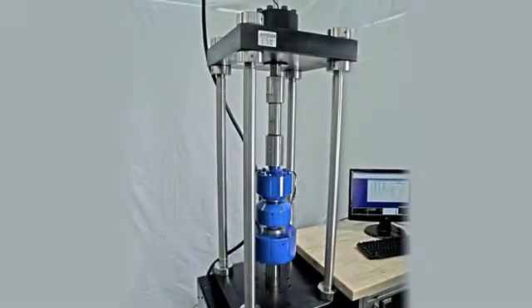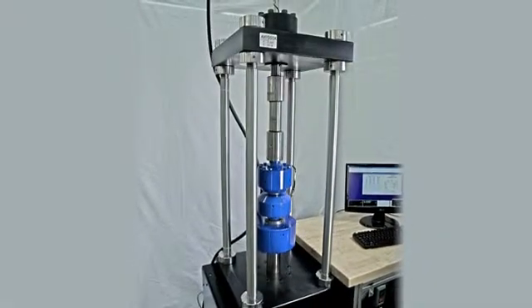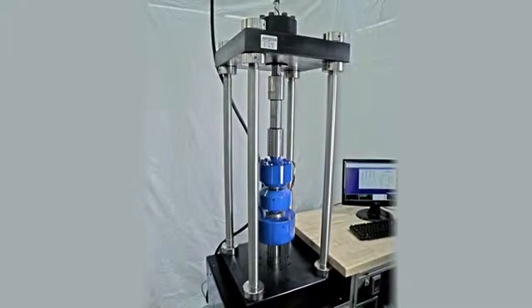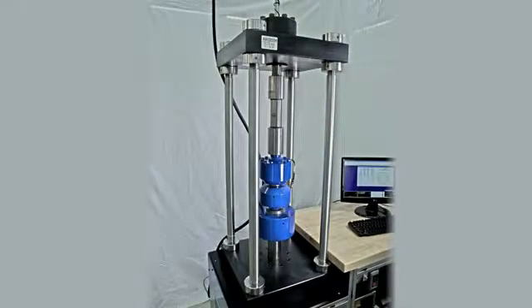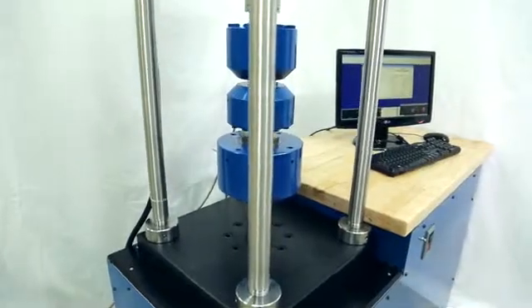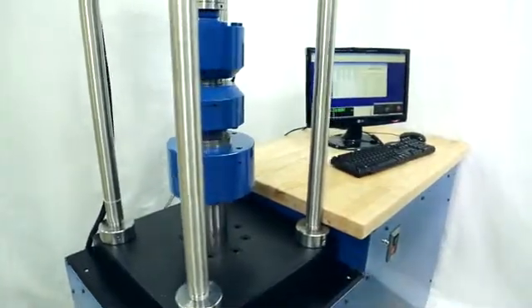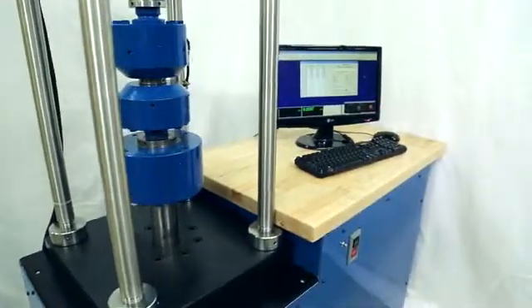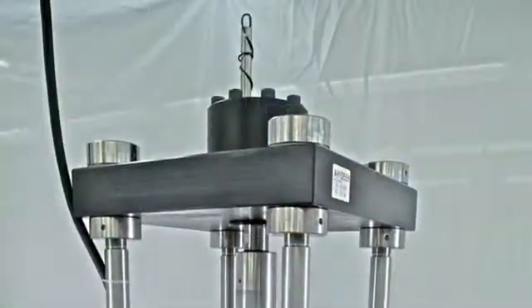It is fully capable of performing ASTM E74 and ISO 376 test protocols for demanding metrology applications. This system is engineered to reduce uncertainty variables to 0.05 percent or less.